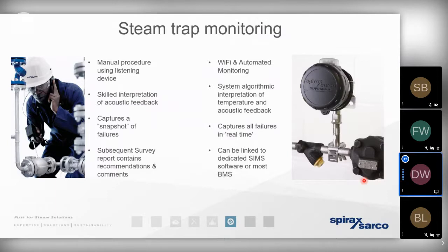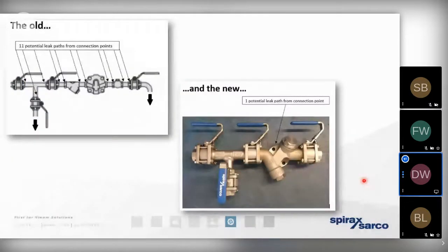So far, we've addressed what we'd refer to as a traditional steam trapping station. And we always refer to a steam trapping station because it reminds us that a steam trap should be installed with a number of other ancillaries. For example, the strainer, the check valve, the isolating valves, and so forth. So a traditional steam trapping station can bring a number of challenges because it can be difficult to install. We've got a number of potential leak paths. There's a huge amount of bracketry. We've got the risk of galvanic corrosion as we've got dissimilar metals. All of these components need to be installed in the correct sequence and the correct flow configuration.